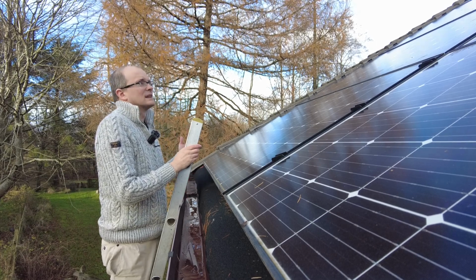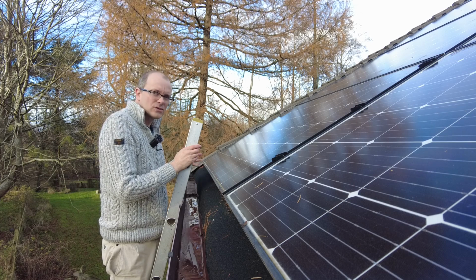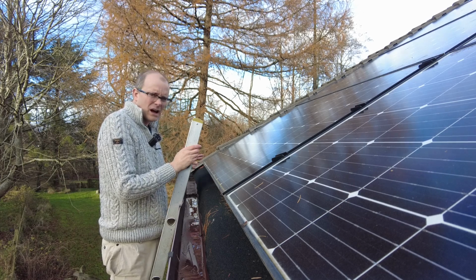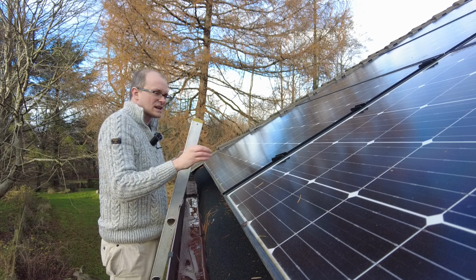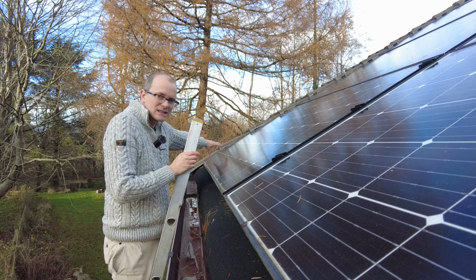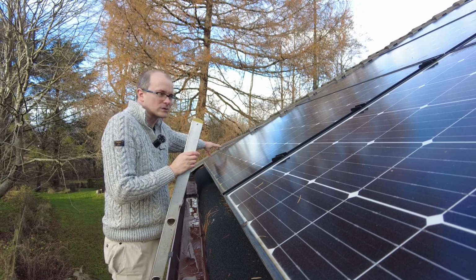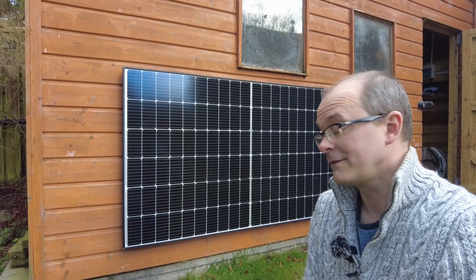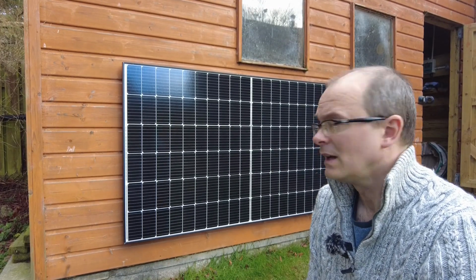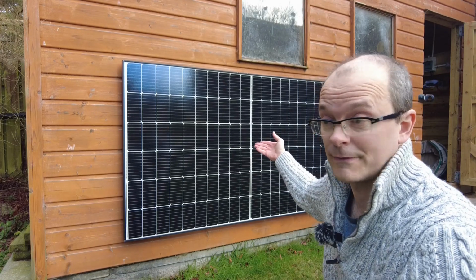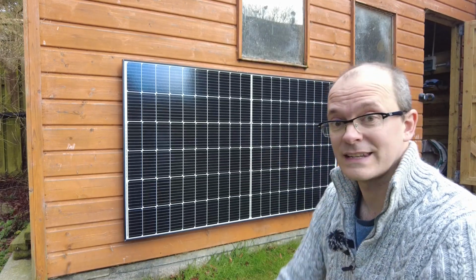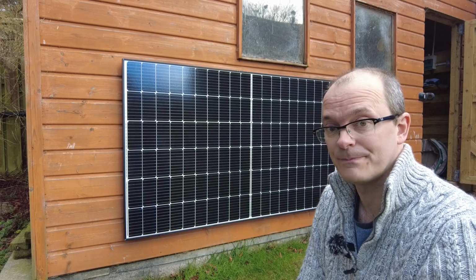And what I'm seeing is that the output from the solar panel has dropped by between half and 2/3, and that suggests that one of these strings has completely failed. So you might very well reasonably ask, why don't I replace the defective solar panel with this rather handy spare solar panel on my shed?